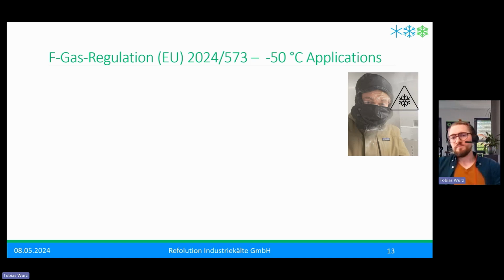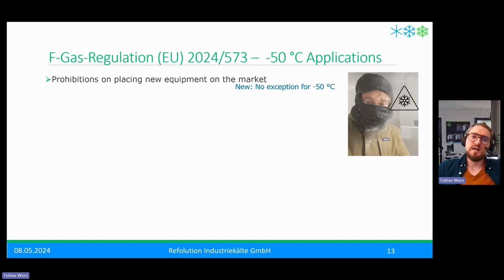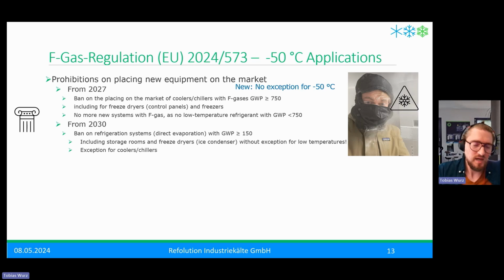So now a special topic, the minus 50 applications, where we are experts, and we especially wanted to talk about this topic. As I explained, with the old regulation we had this exception for minus 50. Now in this prohibition on placing new equipment on the market, we have from 2027 a ban on placing on the market coolers and chillers with F-gases above GWP 750. So as you can see, since R32 has the GWP value from the fourth report of the IPCC, it's still allowed. So you can use this F-gas.